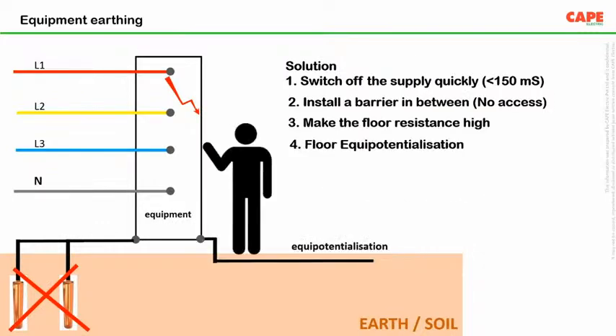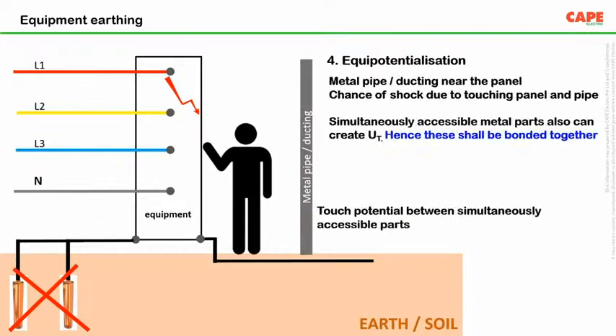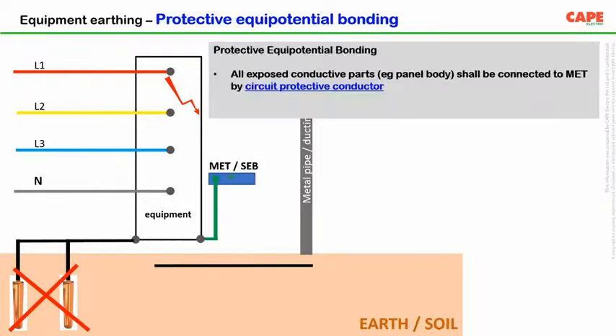safety, what is recommended in the standard is earthing of an equipment means something like this. The equipment, which is called an exposed conductive part, is connected to an earth bus bar. Extraneous conductive parts like metal pipe, the rebar, and all those are connected to a common equipotential bonding bar. Imagine you have a water pipe, an electrical panel and a washing machine. If equipotential bonding is done, the chance of shock is gone.